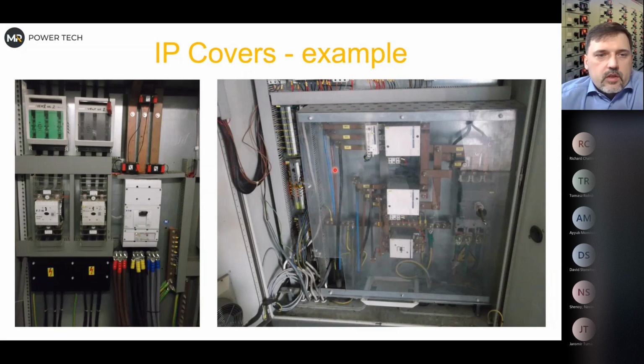And those are from projects where I collected the data. On the left side you see that, okay, this is okay. There are some covers here, but then you open it and you see the main breaker with the cable connection and the main busbar. So this is very bad from a shock hazard point of view and is also increasing the arc flash likelihood. So generally, if you open the doors, you have energized parts. So you need to have all your PPE.